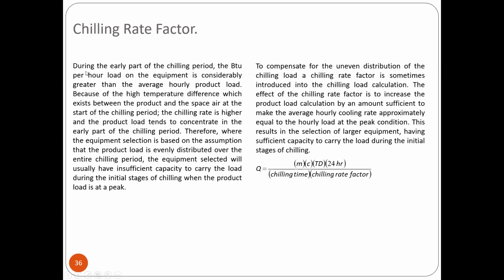So chilling rate factor. During the early part of the chilling period, the BTU per hour load on the equipment is considerably greater than the average hourly product load because of the high temperature difference which exists between the product and the space air at the start of the chilling period. The chilling rate is higher and the product load tends to concentrate in the early part of the chilling. So if the equipment is selected based on the assumption that the product load is evenly distributed over the chilling period, the equipment selected will usually have insufficient capacity to carry the load during initial stages of the chilling when the product load is at peak.